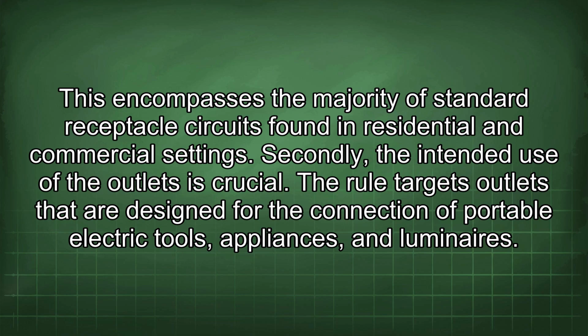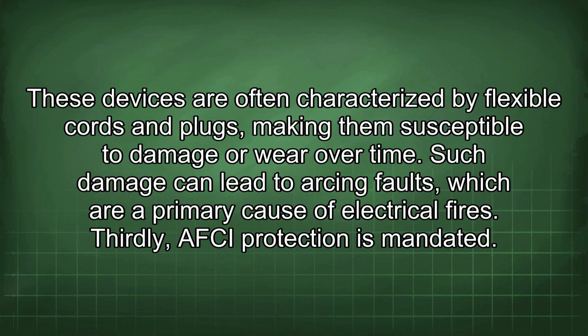Secondly, the intended use of the outlets is crucial. The rule targets outlets that are designed for the connection of portable electric tools, appliances, and luminaires. These devices are often characterized by flexible cords and plugs, making them susceptible to damage or wear over time. Such damage can lead to arcing faults, which are a primary cause of electrical fires.